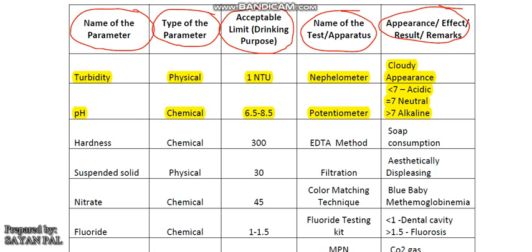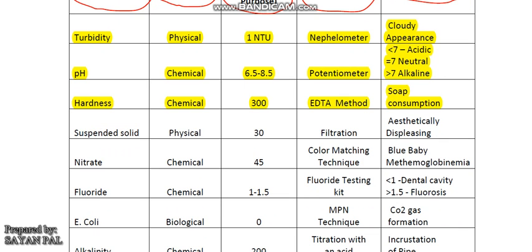Then comes hardness. It is a chemical water quality parameter. Hardness means the concentration of multi-valent metallic cations such as Ca²⁺, Mg²⁺, etc. Its acceptable limit is 300 mg per litre and its cause-for-rejection limit is 600 mg per litre. It is measured by EDTA method with the help of EBT indicator. EDTA means ethylene diamine tetra acetic acid and EBT indicator is eriochrome black T. Hard water means more soap consumption.